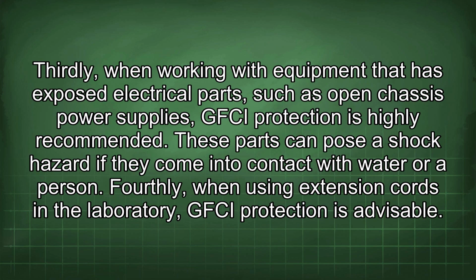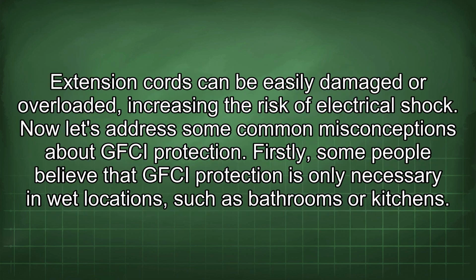Thirdly, when working with equipment that has exposed electrical parts, such as open chassis power supplies, GFCI protection is highly recommended. These parts can pose a shock hazard if they come into contact with water or a person. Fourthly, when using extension cords in the laboratory, GFCI protection is advisable. Extension cords can be easily damaged or overloaded, increasing the risk of electrical shock.